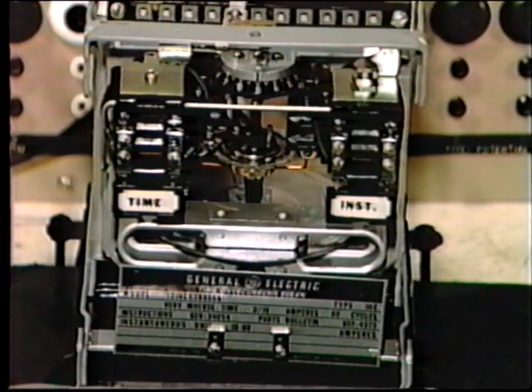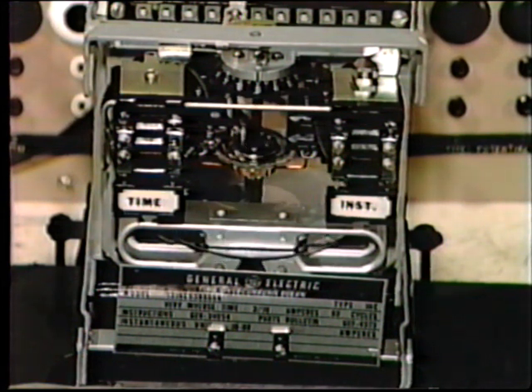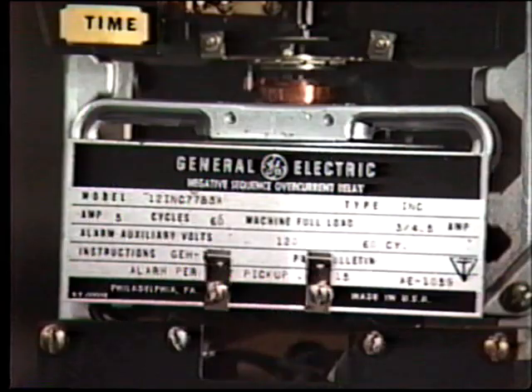The vast majority of relays which are installed on the power system and with which we are familiar are electromechanical relays. The incoming measured signal is fed into a magnetic circuit, which produces mechanical action to operate contacts. These electromechanical relays have proved to be extremely reliable over the years, and in many cases have become quite sophisticated, as those of you who are involved in test and calibration are most certainly aware of.